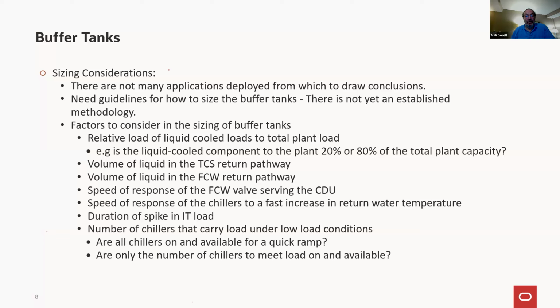Likewise, for the facility cooling water, you can also have a massive return pathway because the pipes get bigger and bigger as you get closer to the plant. And if you have a long distance to travel, that's your natural buffer already. So that plays into the calculation. If I need additional buffering, what size tank do I put in my system? So the sizing and the volume is an issue, but you also have at the CDU level, you're mixing facility cooling water to get the temperature of the technology cooling loop at the right value.